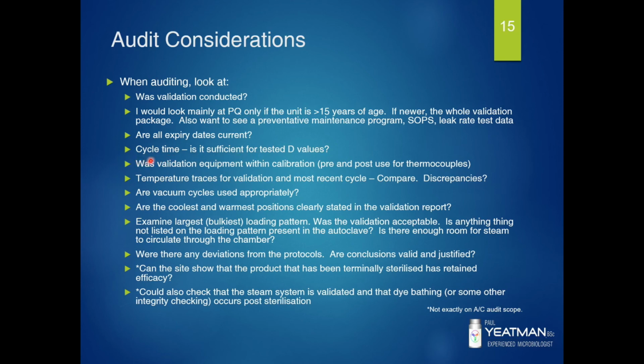Your cycle time, is it sufficient for the tested D values? So if you've got a D value of 1.5, is the autoclave runtime longer than about 11 minutes? Typically you'd find your cycles are 20 minutes long, so typically the answer would be yes, but there's something you need to look at. Was validation of equipment within calibration?